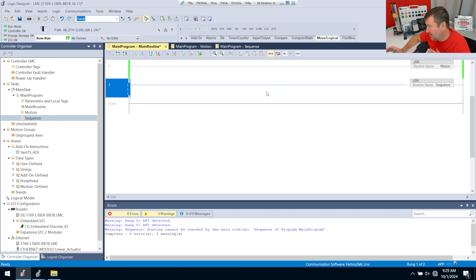and then go and grab that sequence routine and do not hit the finalize button, just so you can get a good mental snapshot. This is something we do in our in-person class. Right now we have no green bars, and I always tell people, they always go for the obvious. They're like, yeah, the routine's not being scanned. I'm like, okay, but next week, what does it mean? If you don't know what I mean when I say next week, it's when you're back at the plant. What does that tell us? It could be the routine's not being scanned, but also I want your eyes to come right over here and make sure that you're not offline, because I have hundreds of hours, cable laying in the floor, forgot to turn the machine back on, didn't go back online, but we are online. So when we hit the finalize button, we're going to immediately get green bars. And now we know that we're good to go.